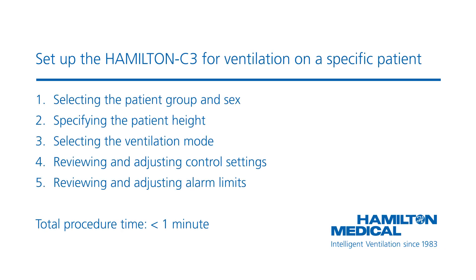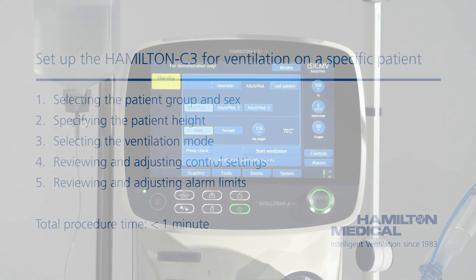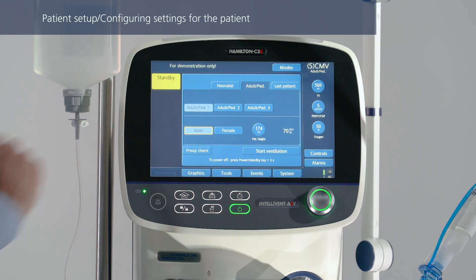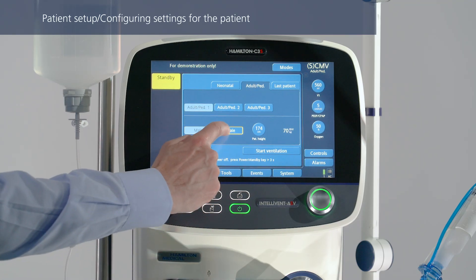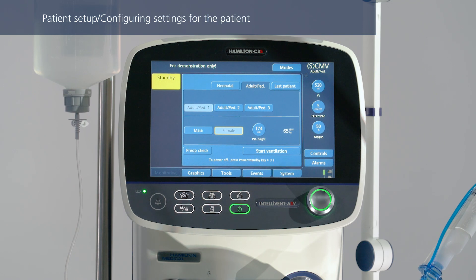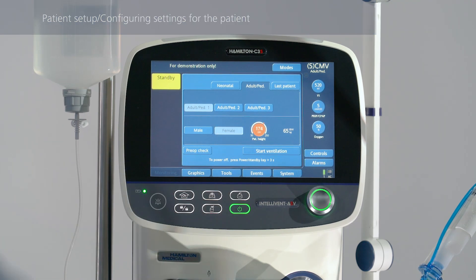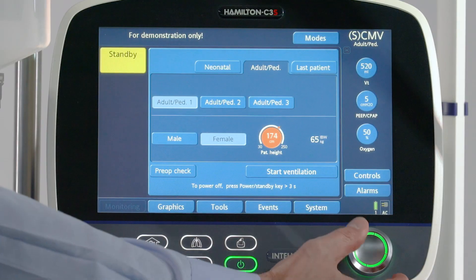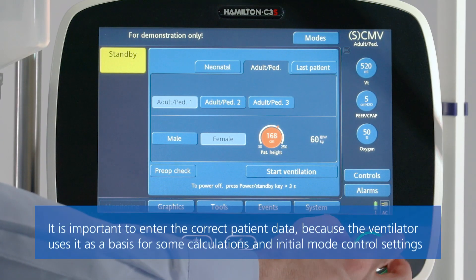Setting up ventilation generally takes just a few steps. You can complete the whole procedure in less than one minute. Before connecting a new patient to the ventilator, select the right patient group and sex, and then specify the patient's height. The ventilator calculates the patient's ideal body weight.